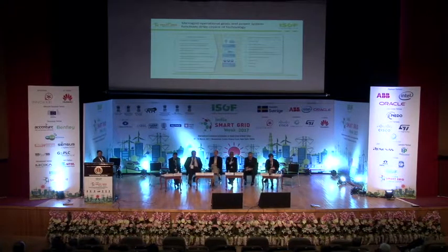So this is basically the operational goals and power system function drivers, which actually drive the choice of technology. What we see is that there are basically 8 S which can be catered to by microgrid technology, and those are stabilizing, spinning reserve, STATCOM, that is static synchronous compensation, seamless transition between island and grid-connected states, standalone operations, smoothing, shaving, and shifting.